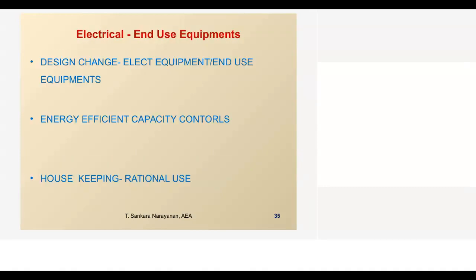So the next is end-use equipment. Whenever we think of motors, there has to be a design change in electrical equipment. This design change we have seen already in the motors. In transformers, there is not much variation except the amorphous core transformer which has come. This has resulted in a lower no-load loss. Similarly, the connected equipment should also have higher efficiency. So we can have a high efficiency pump, a better compressor or a fan. All this equipment will lead to kWh savings.